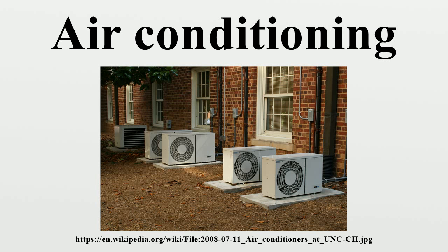When the heat pump is in heating mode, the indoor evaporator coil switches roles and becomes the condenser coil, producing heat. The outdoor condenser unit also switches roles to serve as the evaporator, and discharges cold air. Air source heat pumps are more popular in milder winter climates where the temperature is frequently in the range of 40 to 55 degrees Fahrenheit, because heat pumps become inefficient in more extreme cold.